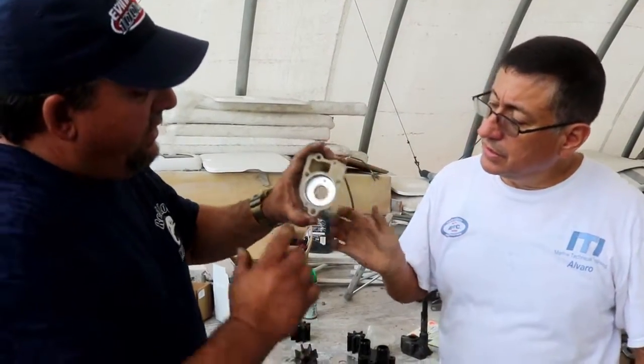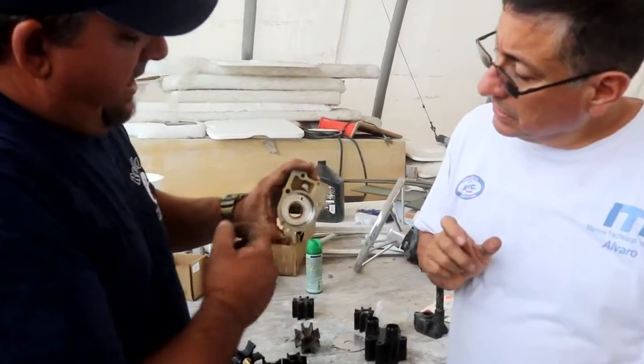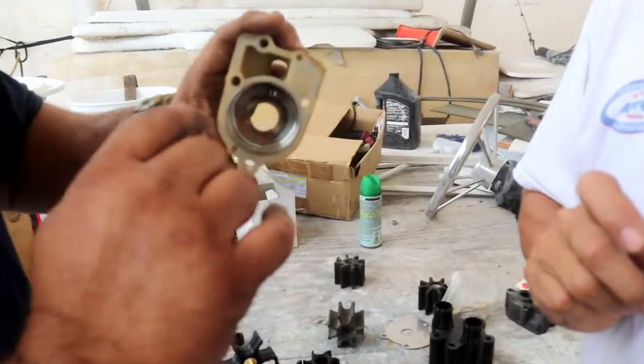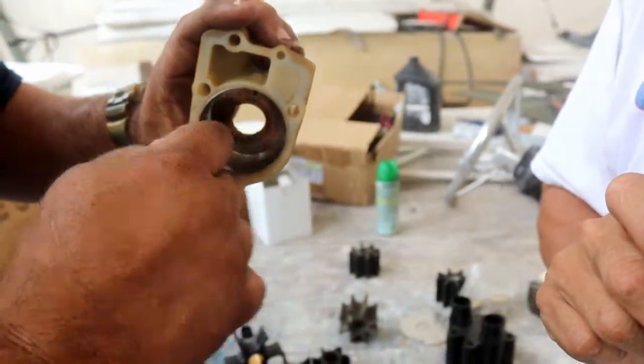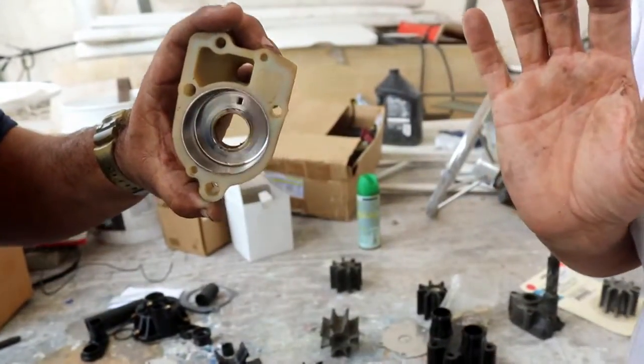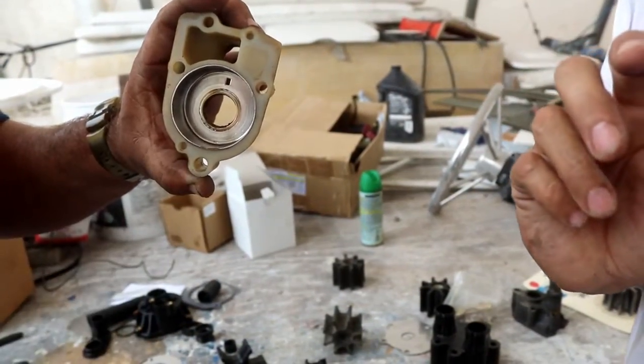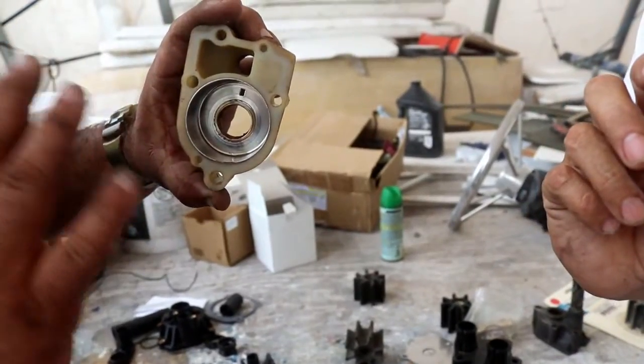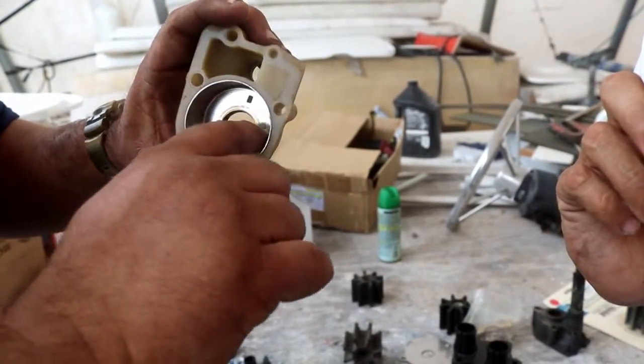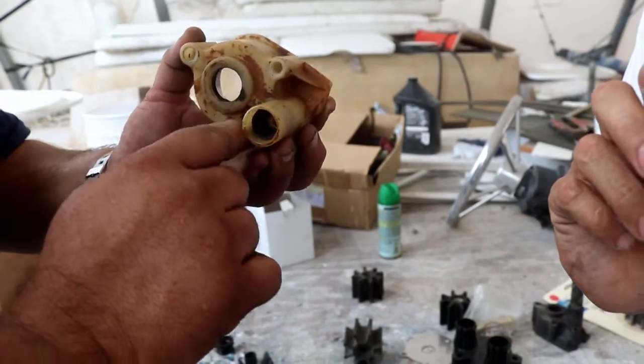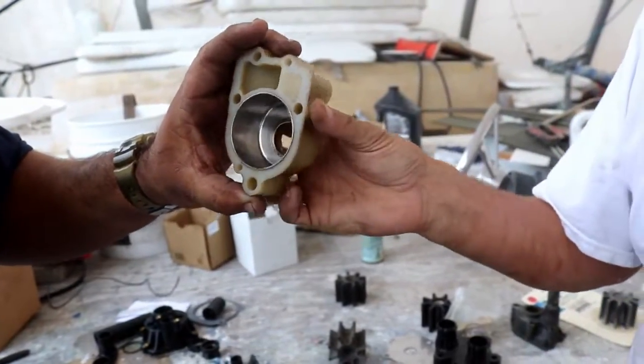So the housing here, if you notice, is smooth. What happens if you get sand is the sand becomes like sandpaper and it cuts grooves in it and really grinds it out, destroying the impeller and the housing. And if you run out of water, this housing will get so hot it'll actually melt the plastic all the way around, and the plastic gets deformed.